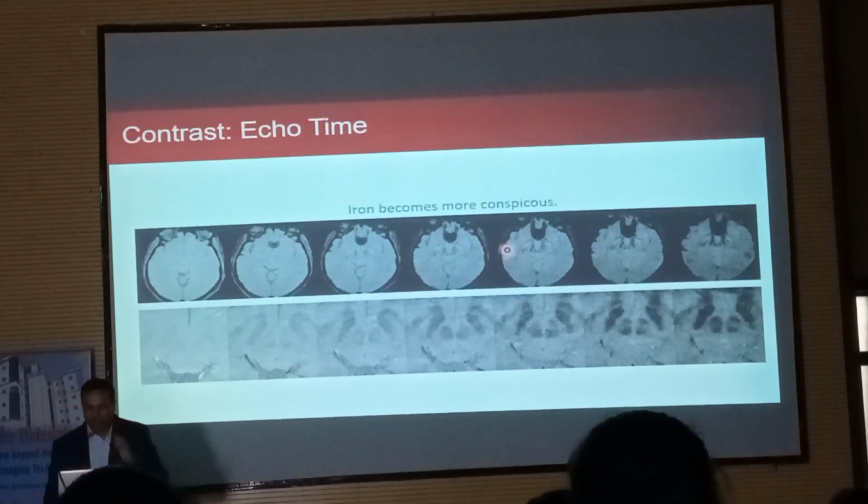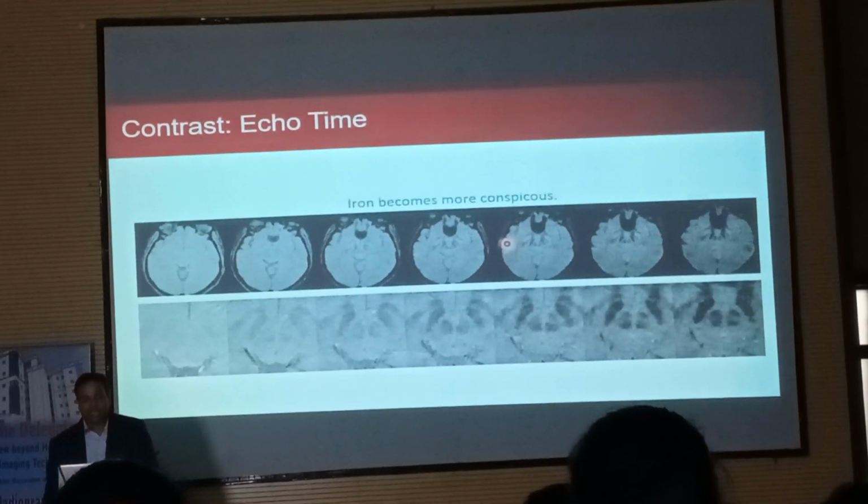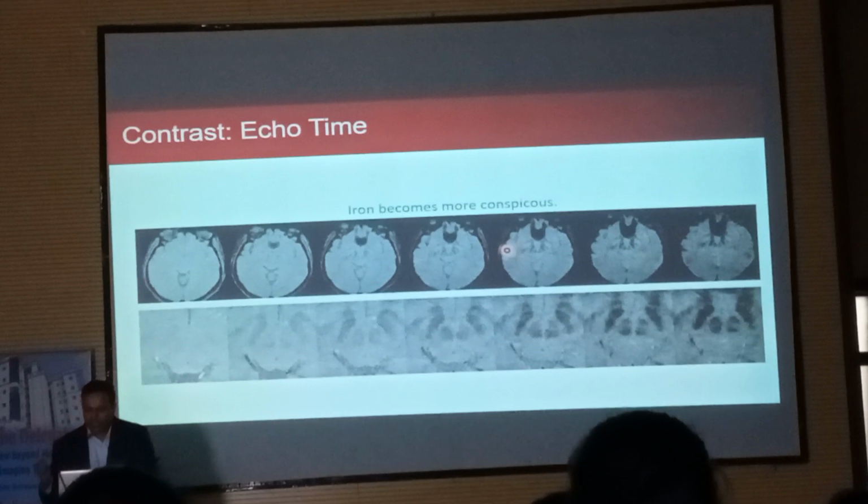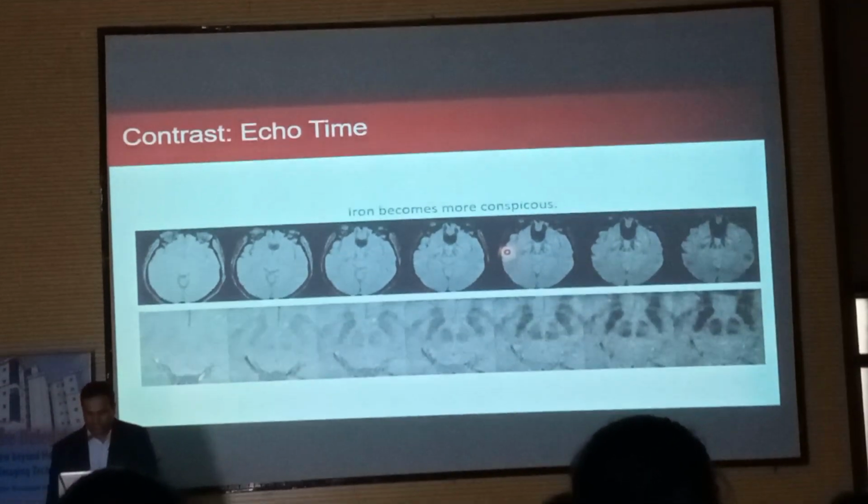Similarly, echo time: if you want to increase the contrast, you need to play with the echo time. So if you wait for a longer TE, you will have increased contrast.